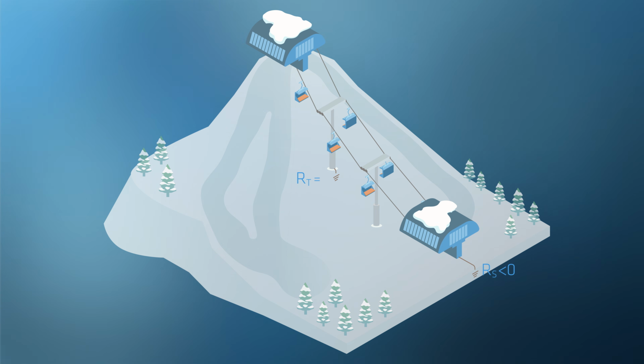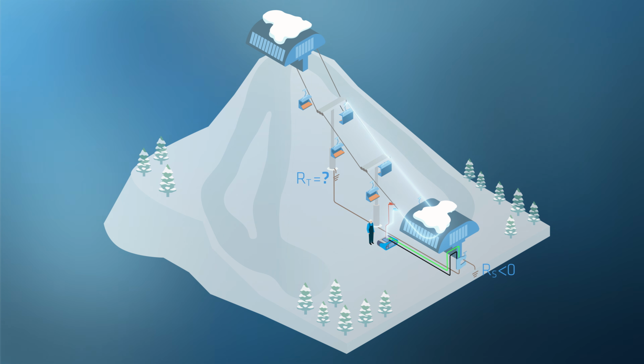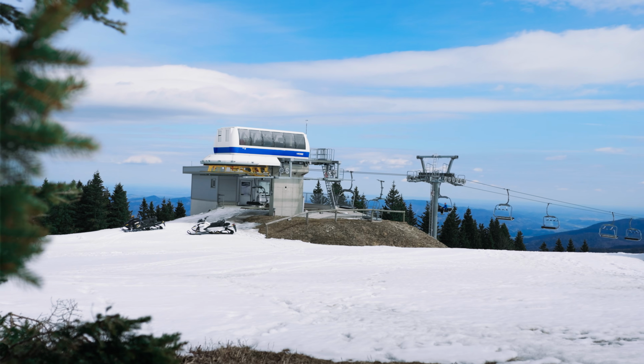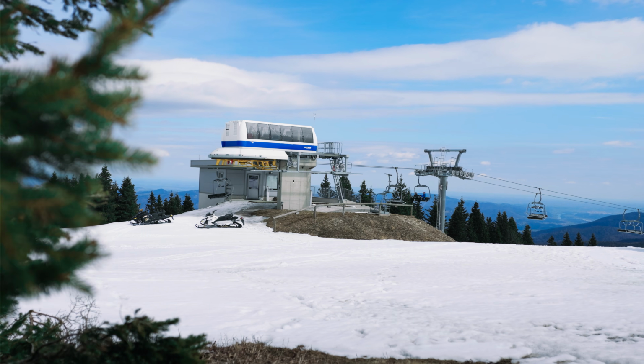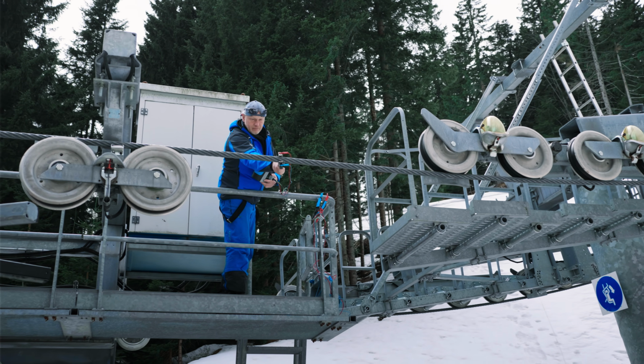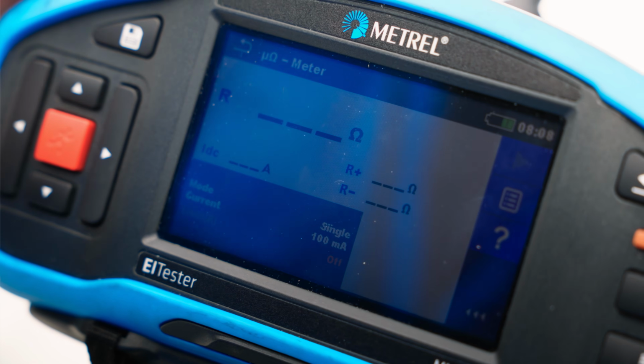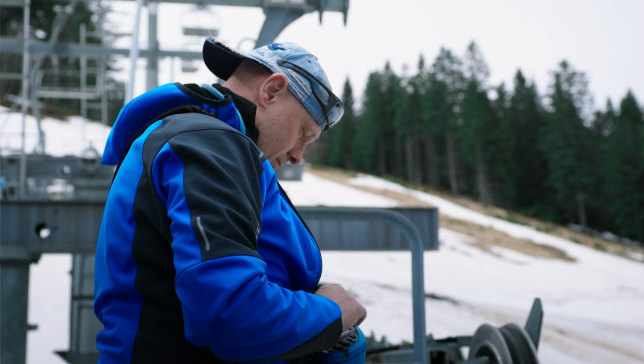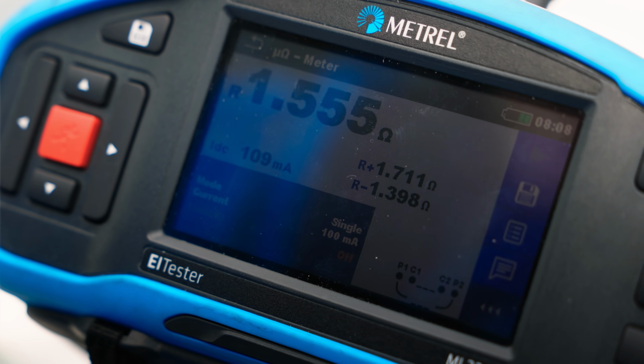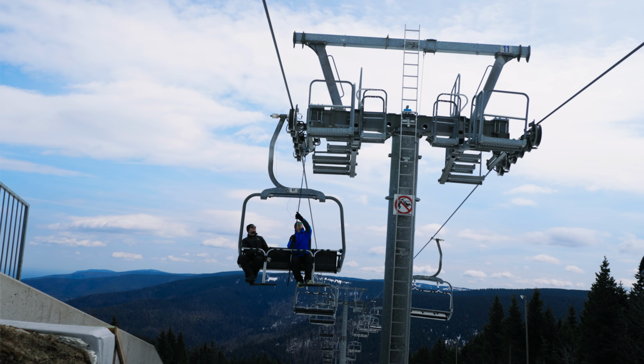Some ski lifts are grounded in a different manner and have all the towers interconnected with metal straps, all the way from the top to the bottom station. For such situations, the MI3288 tester's microohm mode with 2 amps direct current mode should be used. Using the 4-wire measurement method is essential, as it ensures high accuracy even when the electrical contact between the measuring accessories and the test object is poor. The manner of performing the measurements is the same as for other kinds of ski lifts.